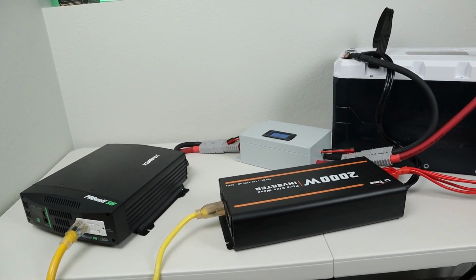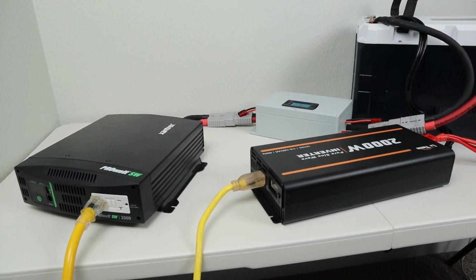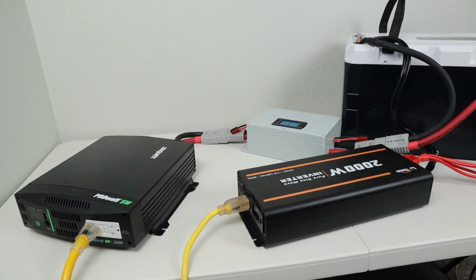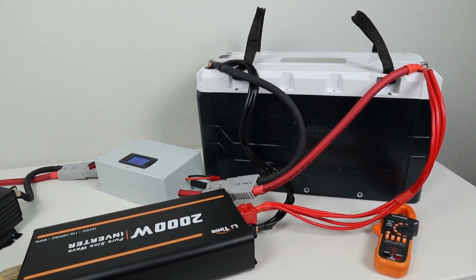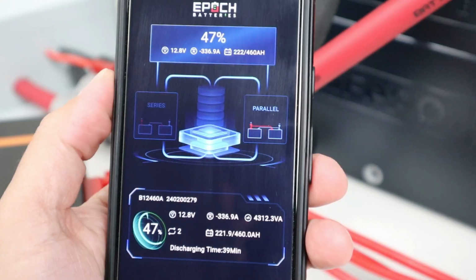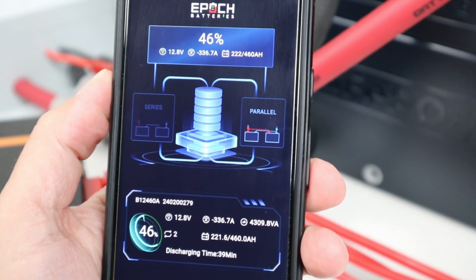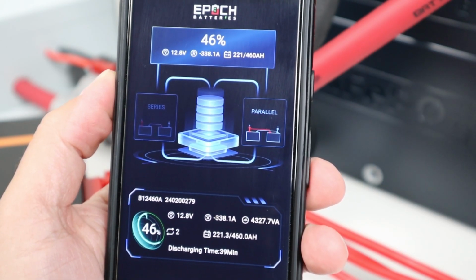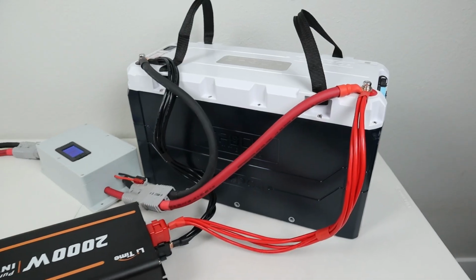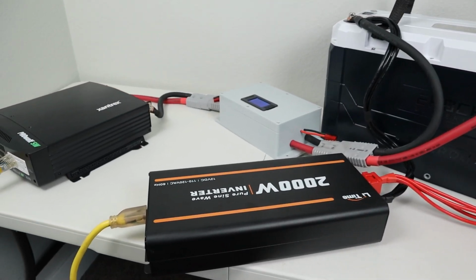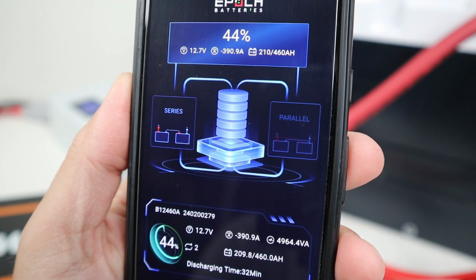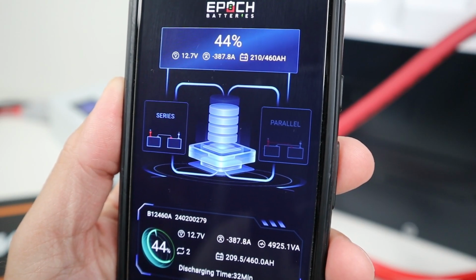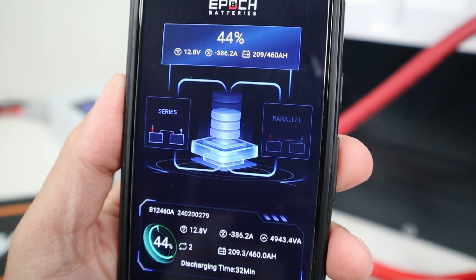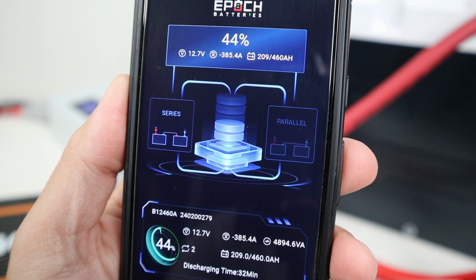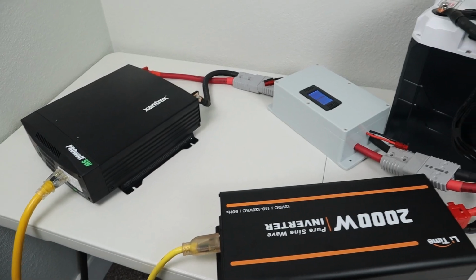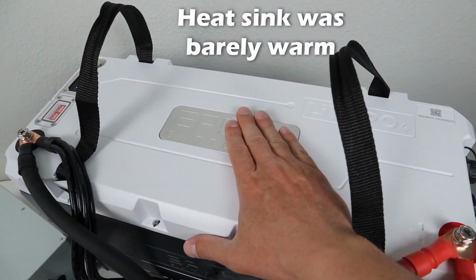In the next test, I wanted to see if this battery could handle the continuous discharge rate of 300 amps without an issue. So I connected up two separate 2,000 watt inverters and kicked on a load. The first load was right around 335 amps, and I let this run for about 10 minutes, didn't have any issues. Then I stepped it up even higher to almost 390 amps, almost 5,000 watts of power. My wires were getting a bit toasty here, so I actually decided to stop the test. Didn't want to melt any wires, but very high power output available from this battery.